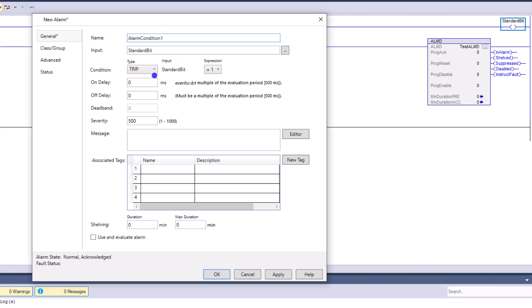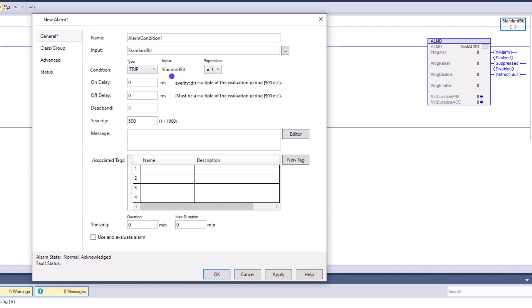So please don't just skip through this video or nothing like that. There are going to be some differences in the ALMD and the Alarm Manager alarm. And why I prefer still an ALMD, I will go ahead and address that. So keep in mind the trip right here, you can put, if it's an analog value, you can put a high high, a high, a low, low low. So in this case, it's just a standard Boolean bit. So this is going to be a trip and we can change the expression from a one to a zero. If we want to alarm on a zero, like say if a bit was held true and if it ever dropped it with alarm, we could do that as well.